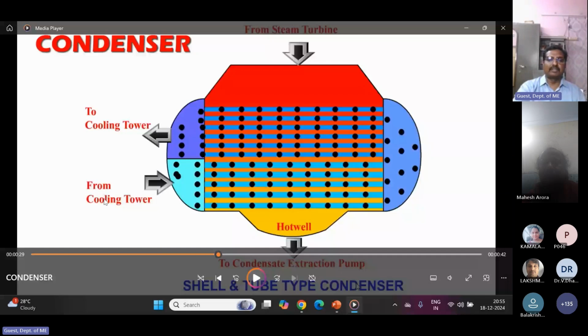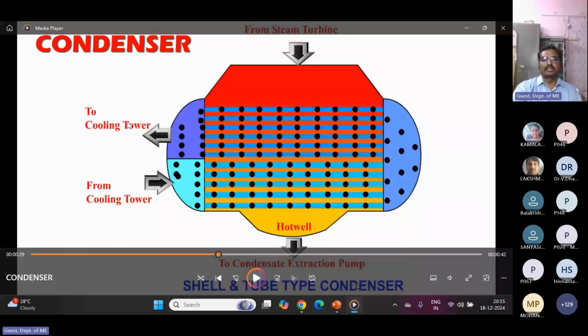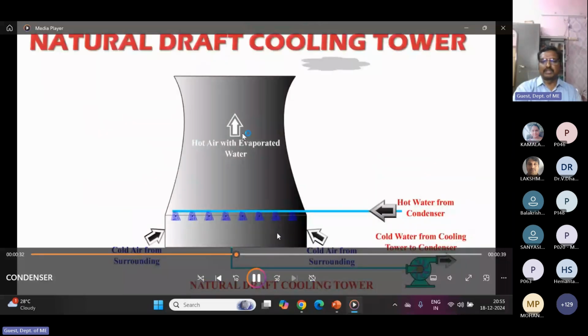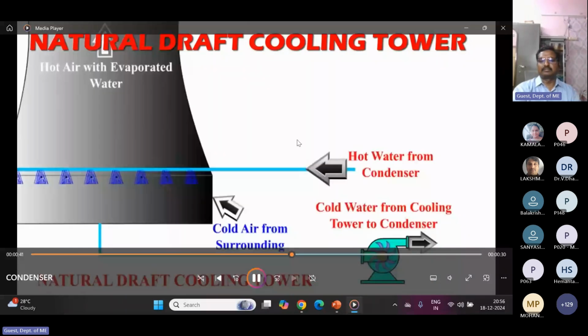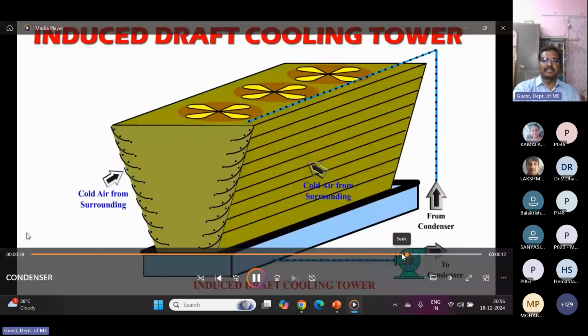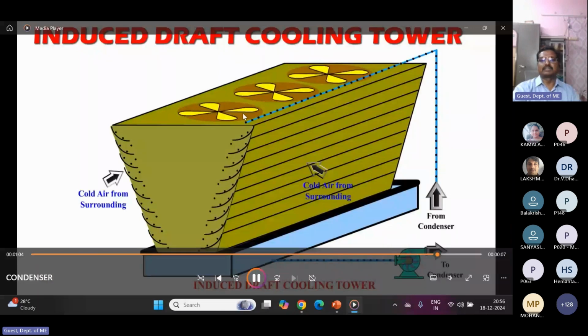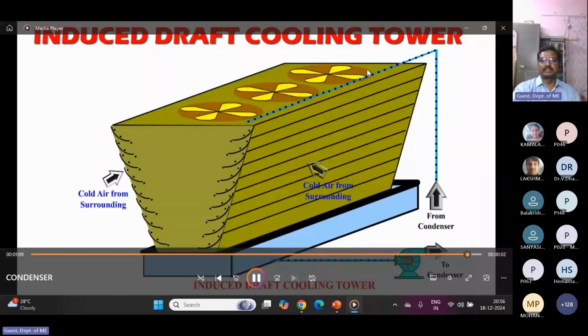In the case of a cooling tower, the water which is coming out from the condenser is sent back to the cooling tower. Cooling towers are basically of two types, natural and artificial. Those very big shells you observe are all natural cooling towers. In that cooling tower, the water falls freely down. Atmospheric ambient air flows upward and removes the heat energy, and the cold water is supplied back to the condenser. This is the cooling tower. The water is sprayed and the heat goes out. These are artificial cooling towers. They run with the help of fans. These are all small size.